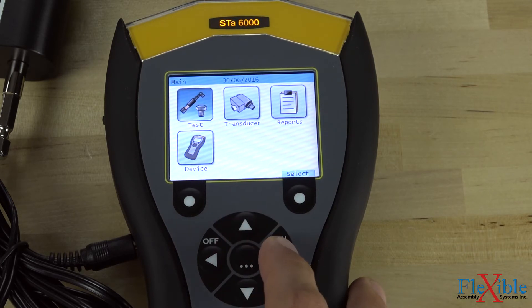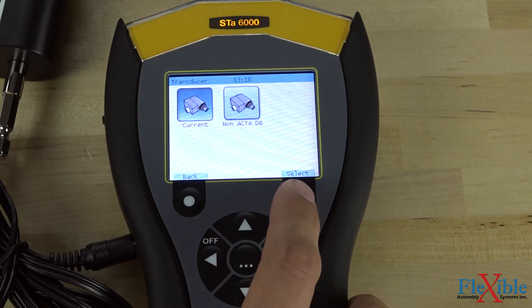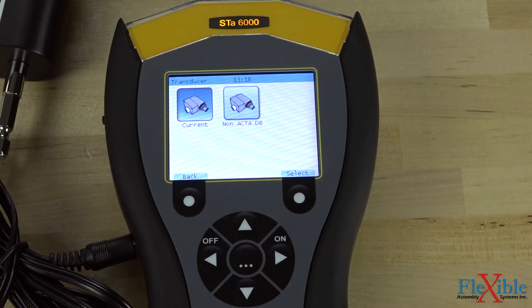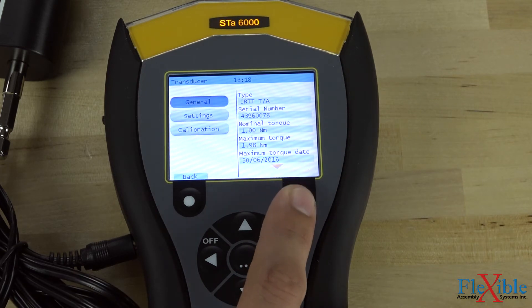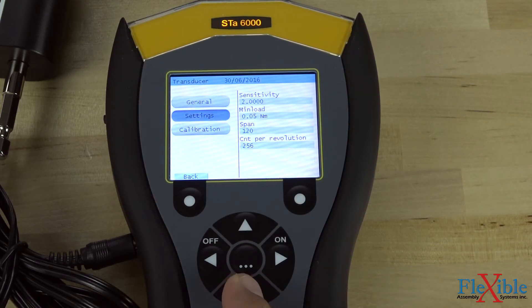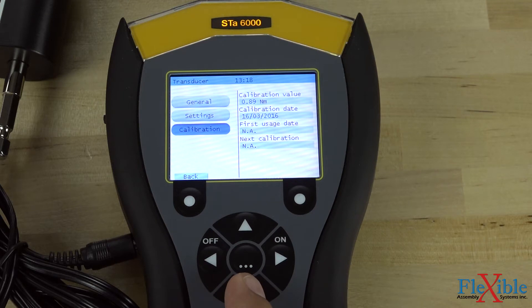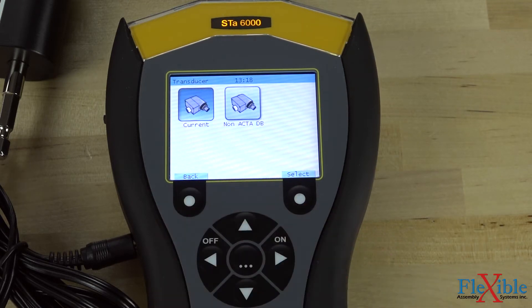To confirm our transducer settings, navigate to the transducer menu and press select. Press select again on 'current' and you will see all the information, settings, and calibration data specific to that transducer. Let's back out to the main menu again.